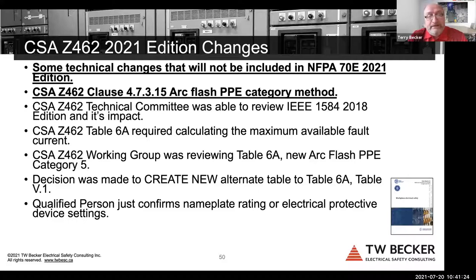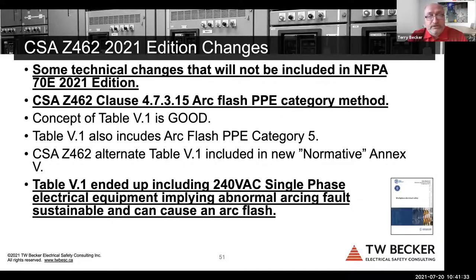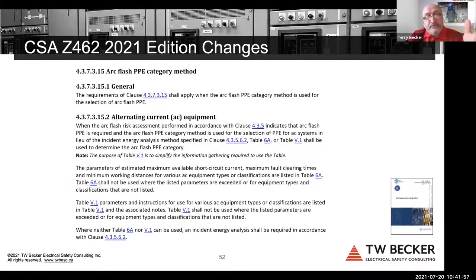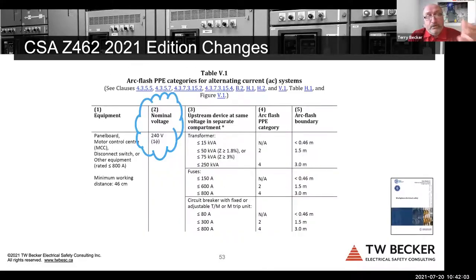I like the idea, but I totally disagreed with the table when we added 240 volt single phase electrical equipment, right? So I do not support this. There is no IEEE 1584 substantiation. 1584 applies to 208 volt three phase. There is a note, but it's clear that 1584 does not apply to single phase electrical equipment, right? So this is again a technical deviation. This is actually a table that's embedded in an annex in Z462, but it is normative. So in the actual clause content, it says that you can use either of these tables, right? So it's a user decision, and only Table 6A is embedded in the core body of the clause. This is just a short excerpt where the 240 volt was added.